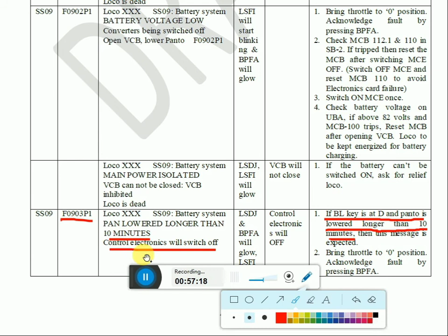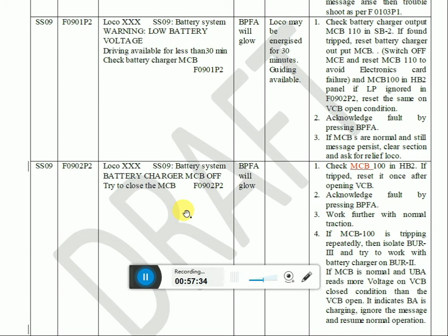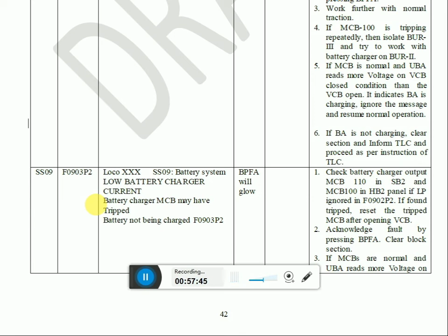If battery voltage drops to 92, we will get a message like this. F0902P2: Battery MCB trip. F0903P2: Low battery charger current, 110 trip or charger not working. F0905P2: Earth fault in battery circuit. If there is any earth fault in the battery circuit and an RTS provision is there, we have to switch off the RTS breaker and try.